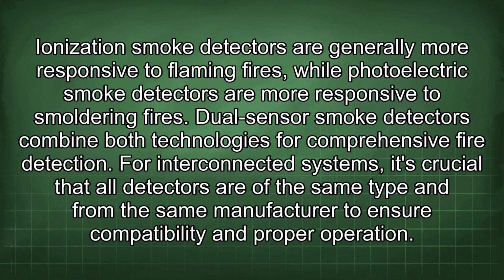Ionization smoke detectors are generally more responsive to flaming fires, while photoelectric smoke detectors are more responsive to smoldering fires. Dual-sensor smoke detectors combine both technologies for comprehensive fire detection. For interconnected systems, it's crucial that all detectors are of the same type and from the same manufacturer to ensure compatibility and proper operation.